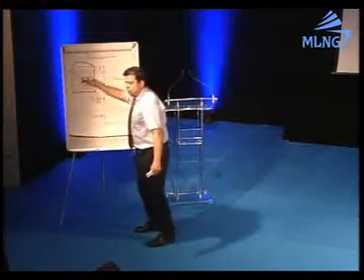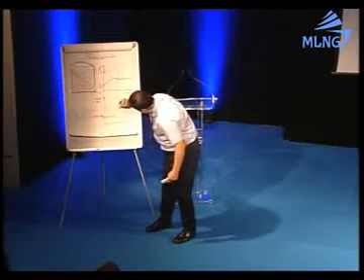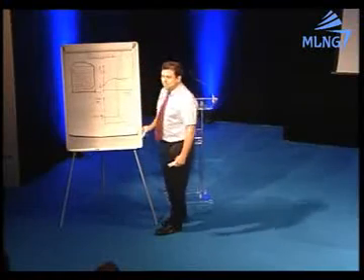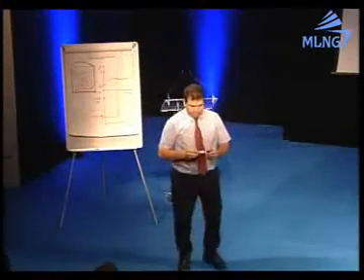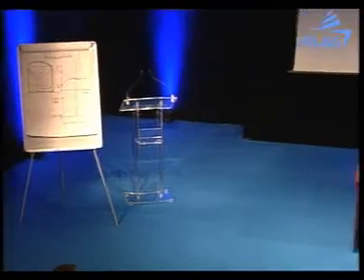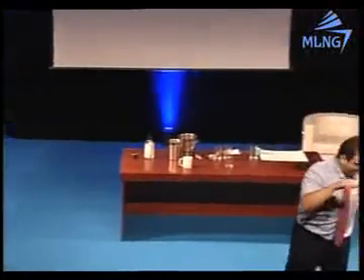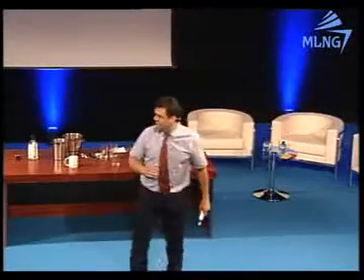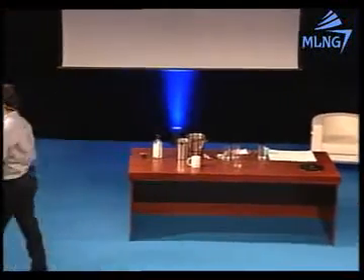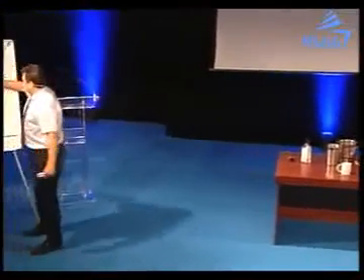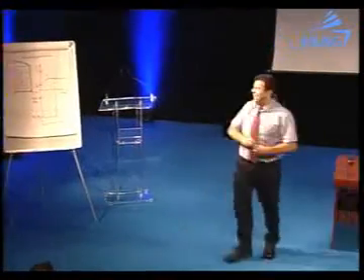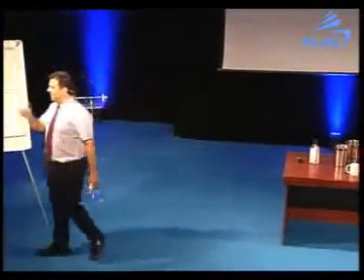When the rollover occurs, it can multiply by 100. The boil-off generated is more than 100 times the typical, the normal or the daily boil-off. So the rollover phenomenon we can control, of course, but this is the explanation. And now with this demonstration, Sophia, water, please.